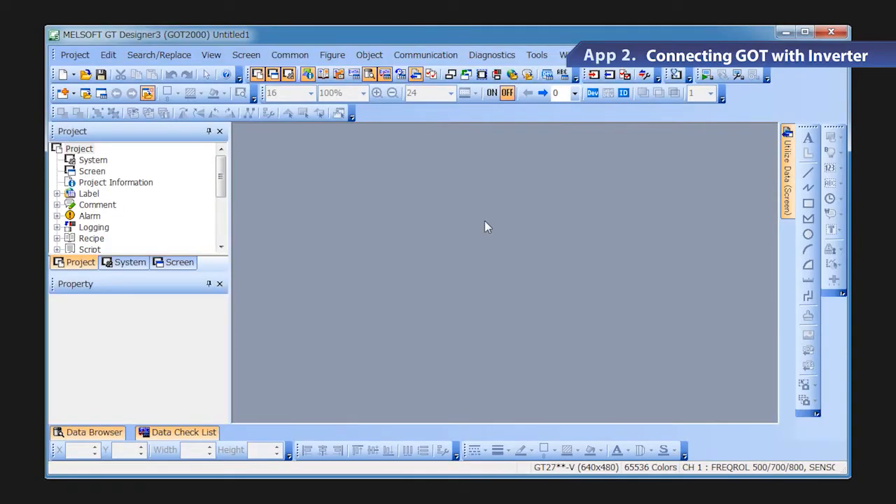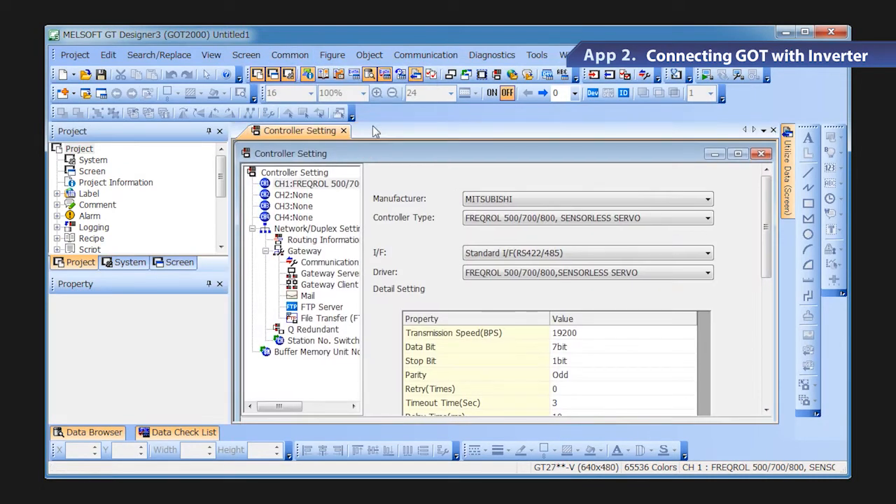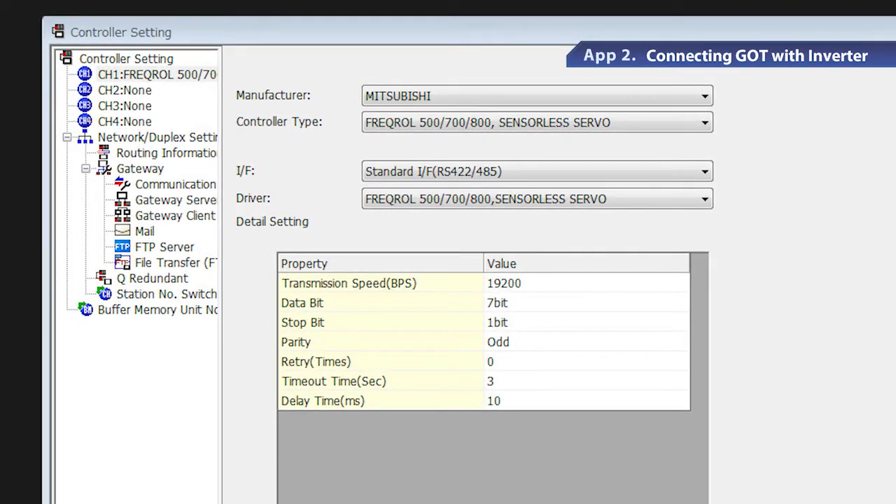Set the channels for the connected devices. Go to the common setting menu and select controller setting. When the controller setting window appears, select the channel number from the list menu. Select Mitsubishi in the manufacturer field and FREQROL 500/700/800, SENSORLESS SERVO for the FR-E700 series inverter in the driver field.